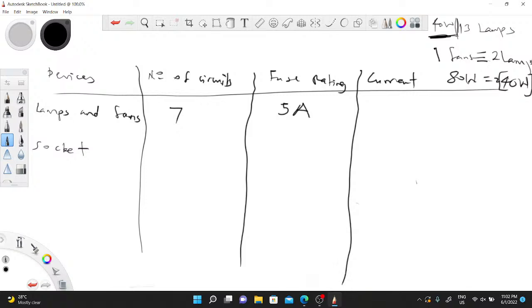If you have your drawing beside you, look at it. For the socket outlets, we connect all sockets in an area less than or equal to 100 square meters together. I repeat, we connect all sockets in an area less than or equal to 100 square meters together.